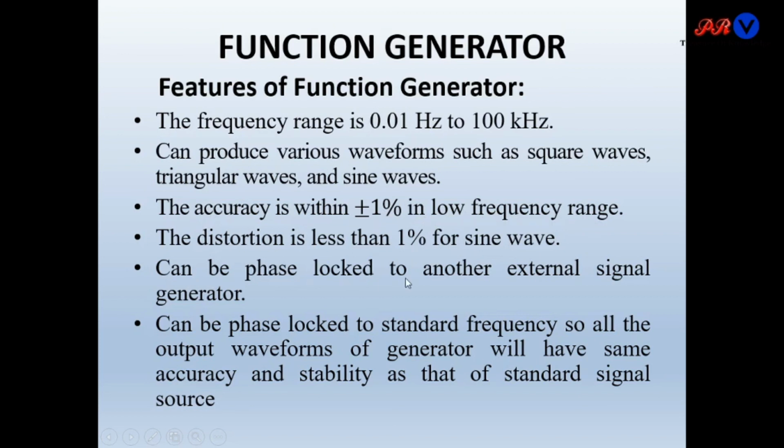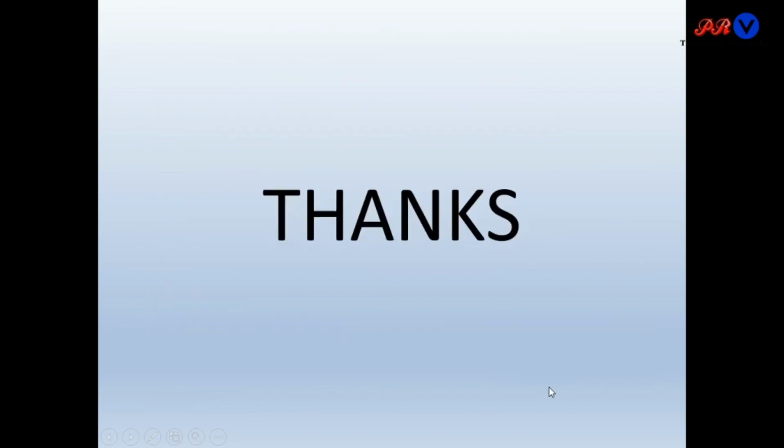They can be phase locked to another external signal generator, means the phase lock to a standard frequency. So, all the output waveforms of the generator will have the same accuracy and stability as that of the standard signal source.